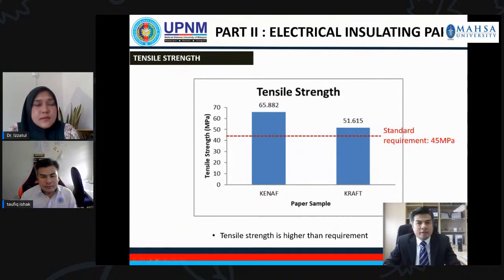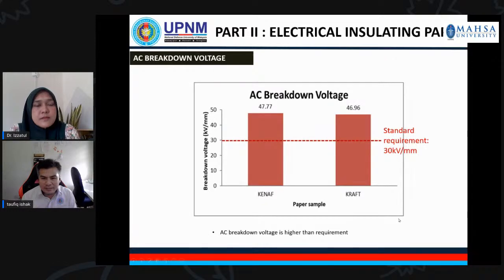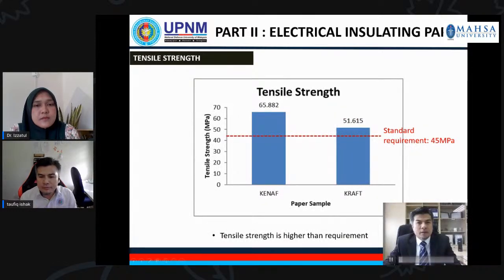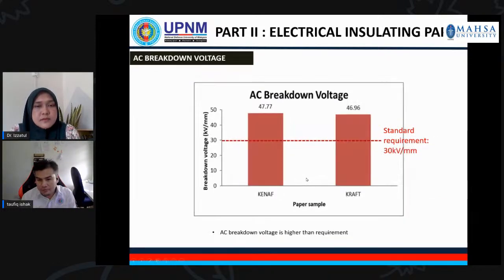in terms of tensile strength, as compared between Kenaf and Kraft, the standard requirement for the insulation paper is actually 45 megapascal. And then from our test, what is surprising is we achieve 65 megapascal for Kenaf, and Kraft paper is 51.6 megapascal, which surpassed the standard. It's quite a promising result for this one.